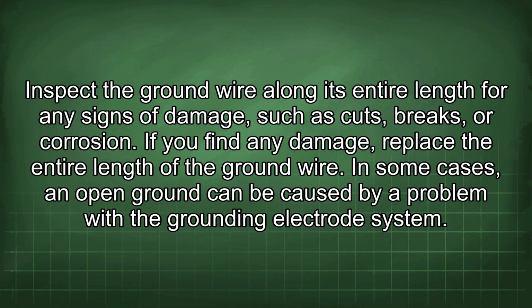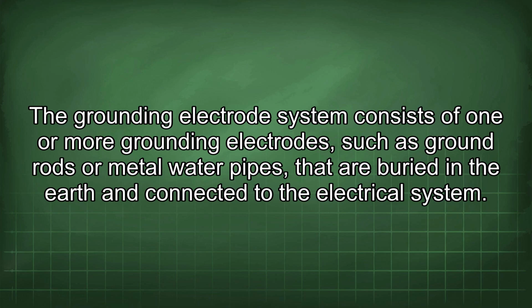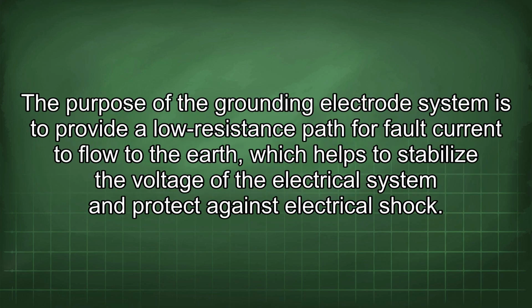In some cases, an open ground can be caused by a problem with the grounding electrode system. The grounding electrode system consists of one or more grounding electrodes, such as ground rods or metal water pipes, that are buried in the earth and connected to the electrical system. The purpose of the grounding electrode system is to provide a low resistance path for fault current to flow to the earth, which helps to stabilize the voltage of the electrical system and protect against electrical shock.